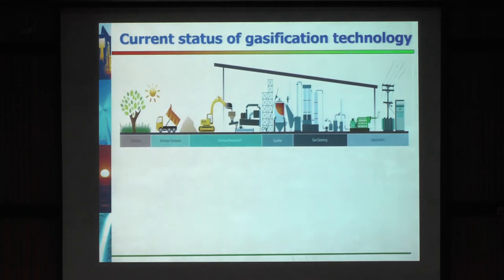This shows the summary of the demonstration plants. Of course, we need to transport the biomass from the field, and then prepare this biomass to be used as feedstock for the gasifier. For biomass preparation, we need to dry the biomass to a moisture content of not over 15% and a size of not over 10 centimeters in order to feed it into these reactors. In these 12 demo projects, we use different kinds of gasifier technology, either down-draft gasifiers or up-draft gasifiers. In some projects, we introduced technology from Europe.